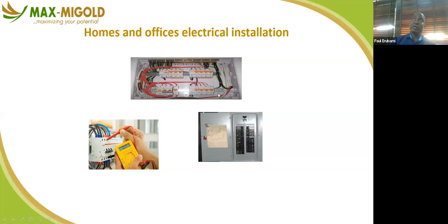So when you go to the distribution board and a section of your installation is cut off, instead of tracing, you just go to the distribution board and see that a breaker has tripped. What you need to do is check what happened, what led to the tripping of that breaker. Before you reset the breaker, you have to be sure that the fault that led to the tripping has been cleared. If you don't know how to go about it, call a professional, a trained electrician or electrical personnel, to come and check. He will use his meter, like the one you are seeing here, to check what the issue is. When the problem is confirmed and resolved, that's when we go back and switch up the breaker that has tripped.